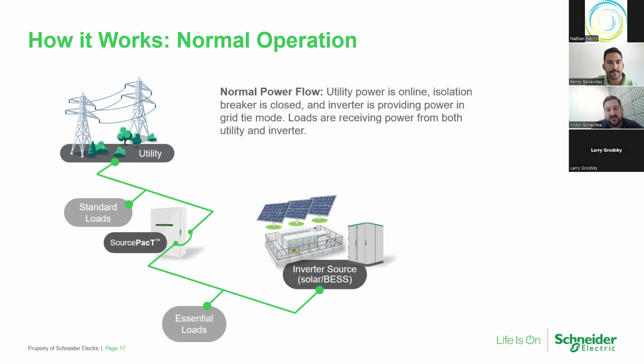There's going to be a service entrance on it, some feeder breakers to some non-backed up loads, but there's going to be one feeder breaker coming off of that load down through a SourcePacT, feeding another board, which you can consider almost like your emergency sub panel, if you're familiar with the way we architect some of these smaller generator systems. On that emergency sub panel that's being fed through SourcePacT, you're also going to have a breaker, and that's where your inverter or your solar is going to be connecting into the system as well.